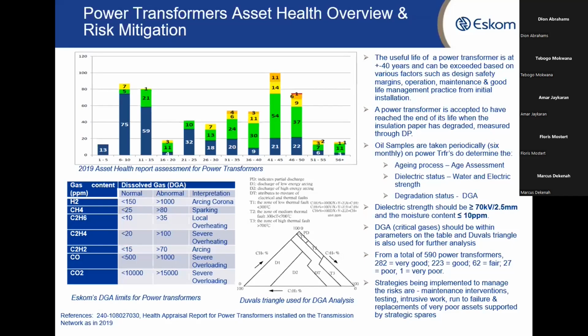However, in between, we also look at your dielectric strength as well as the DGA, which can show you if there's developing faults. And on the table here, it shows some of the limits that we use to determine if we have some of the arcing that is happening or local overheating. And we also use the Duval triangles for further analysis in combination with this DGA that we're picking up from our transformers.